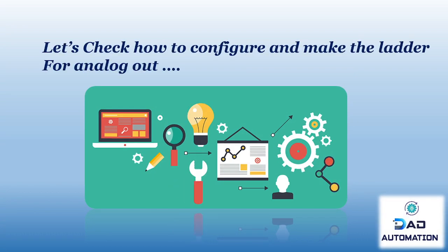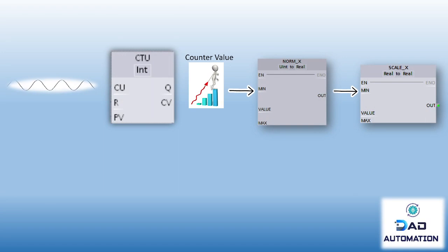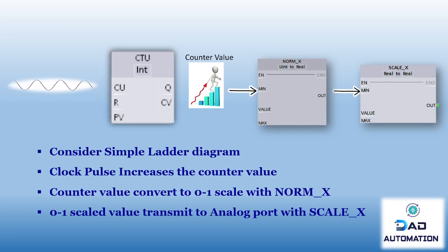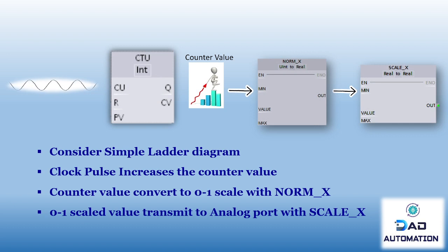Let's check how to configure and build the ladder for analog output data processing. Consider a simple ladder diagram: a clock pulse increases the counter value, the counter value is converted to a 0 to 1 scale using NORM_X, and the 0 to 1 scaled value is transmitted to the analog port using SCALE_X. Let's see how to program analog output in the TIA Portal environment and simulate it to see the output.